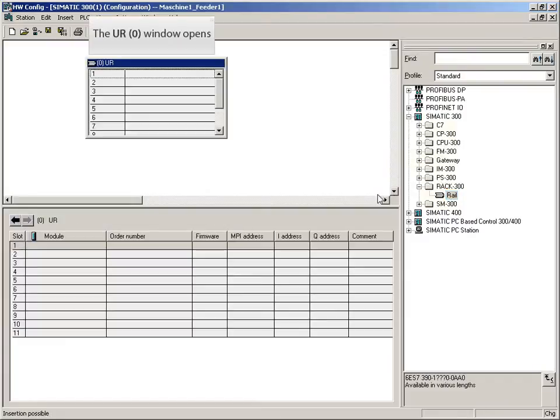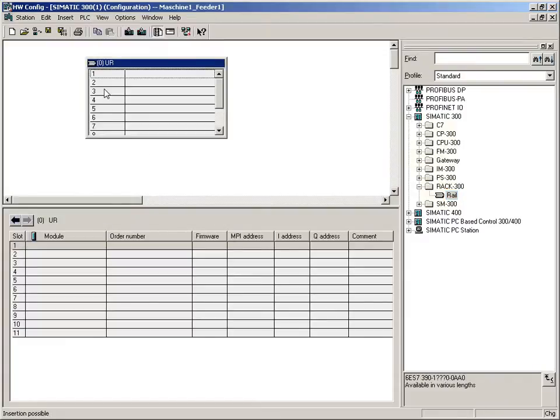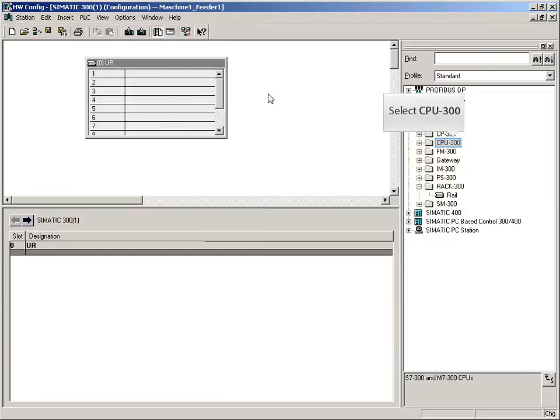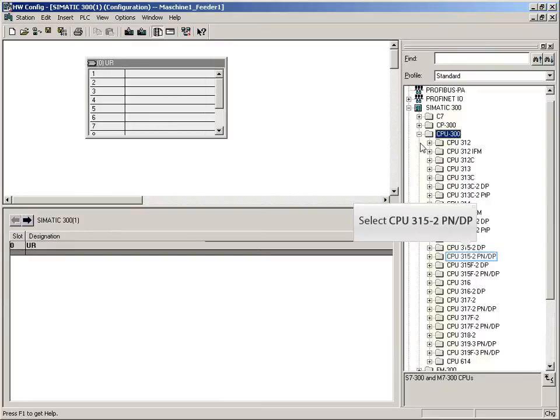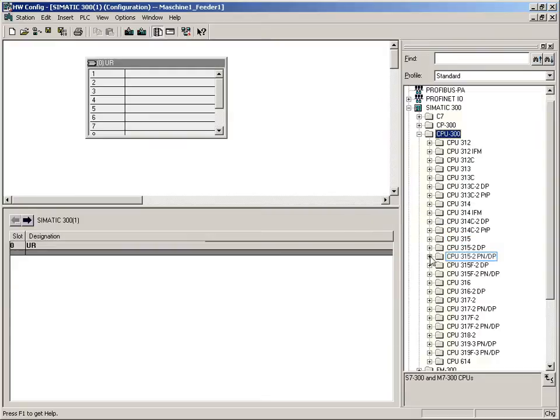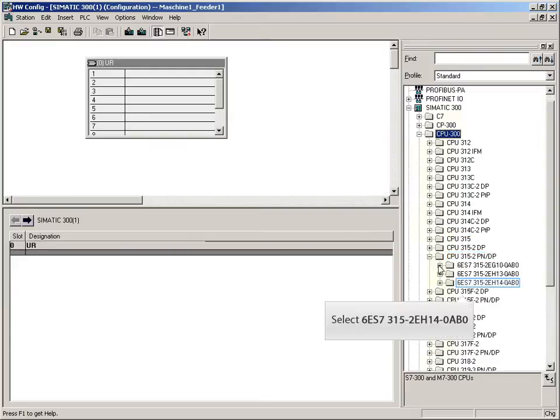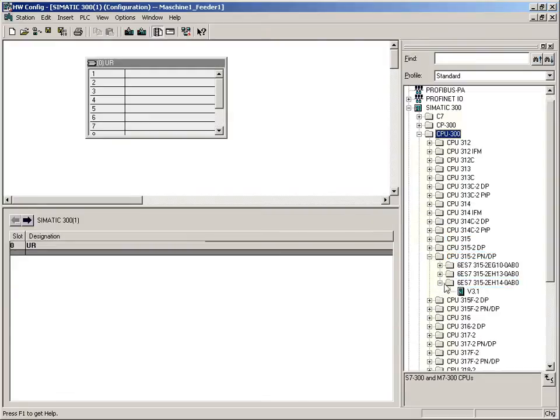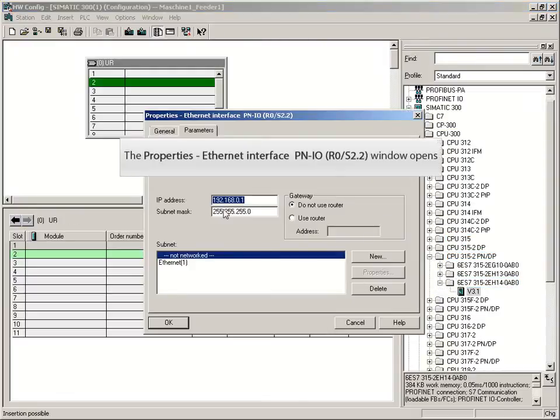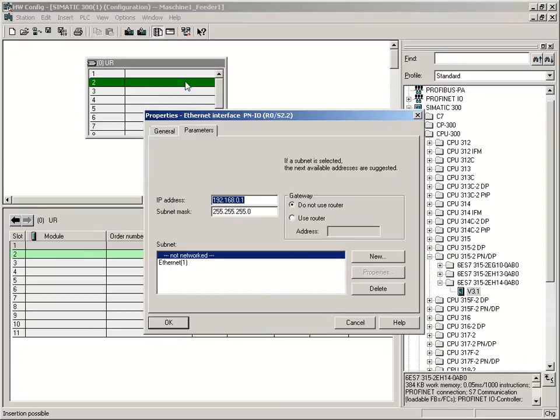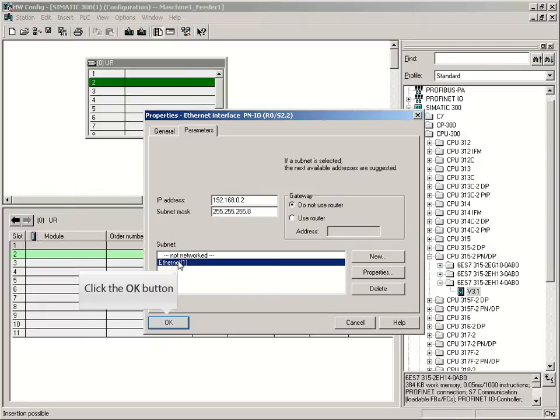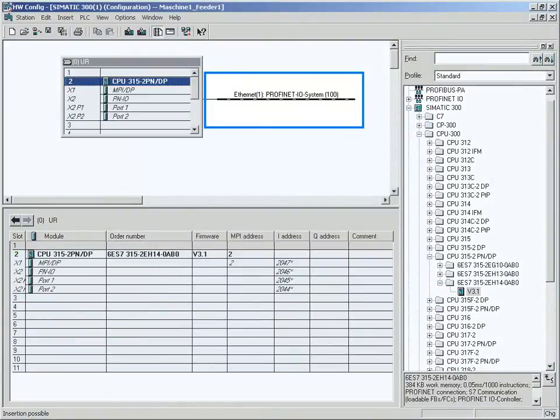You can drag this profile rail here into this field and drop it. Now you will add to this empty rack a CPU. We have here a CPU 315-2 PN/DP and select the CPU, which will be positioned on this location too. Here the CPU is presented. It contains the Ethernet connection which we will mark. Now we have the Profinet system integrated here.